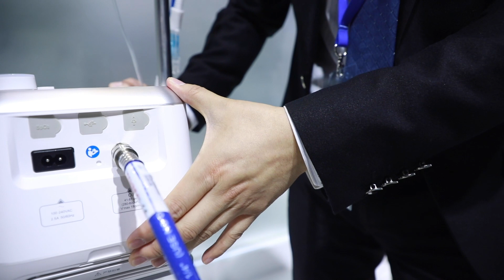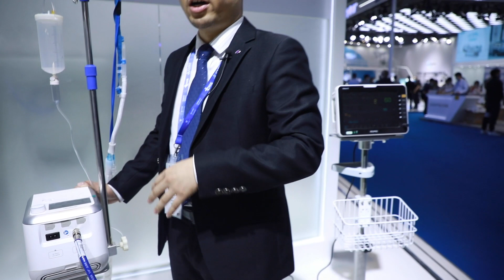Room air through a PM2.5 filter is run by a quiet turbine. The oxygen from central supply and the compressed air by the turbine are mixed as they travel past the flow and oxygen sensor. i7 has a higher flow rate, up to 80 liters per minute, and accurate FiO2 control from 21 to 100%. And then the mixed gas is driven into the water chamber.